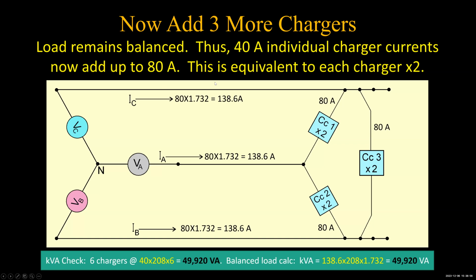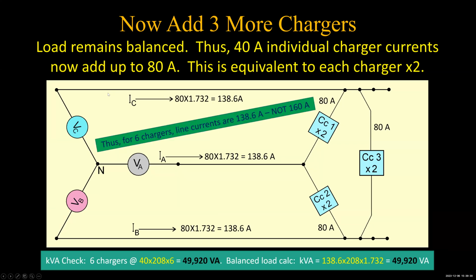So that's one solution to the problem. Pretty clear. I mean, NEC says up to 3 wires in a conduit, this is what their ampacity is, and nobody argues with that. The only argument there is whether your contacts are 90 degree or 75 degree, and whether you're using THWN2 at 90 degrees and have to derate to 75 degrees and all that stuff. That's another story. But the third harmonic stuff is out of the question here with the delta connection. So interesting. So we're good. 138.6, not 160. But if we try to add 3 more, we're going to go over 160, and we can't do that.